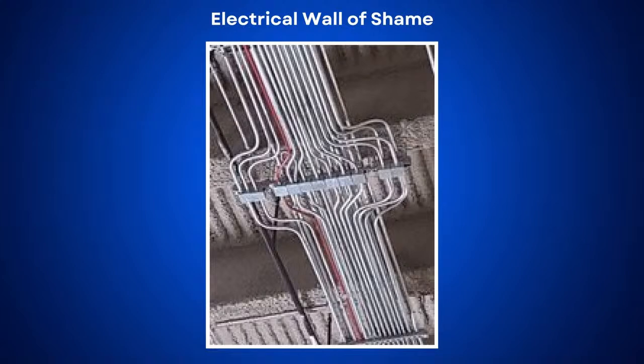I've actually pointed that out before. If you're just using number 10 for your sizing, for like a 20 amp circuit, then you technically don't need to derate or anything, because your number 10, if you go off the 75 degree C column, gets up to 35 amps, then you cut that in half, you're still over 20. You're going off the 90 degree C column for your derating, so then you cut that in half, you're still good for 20. It just depends on how many are in there.